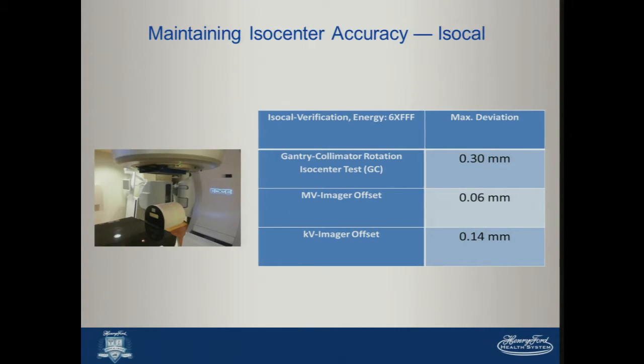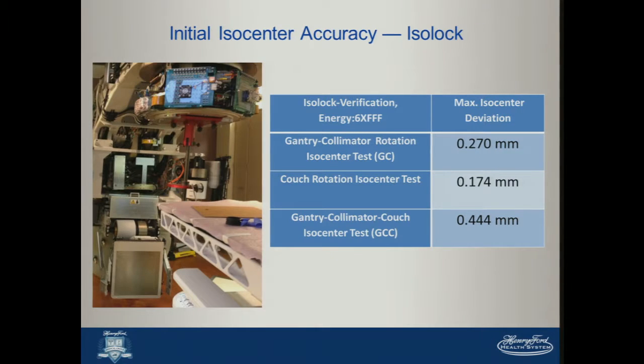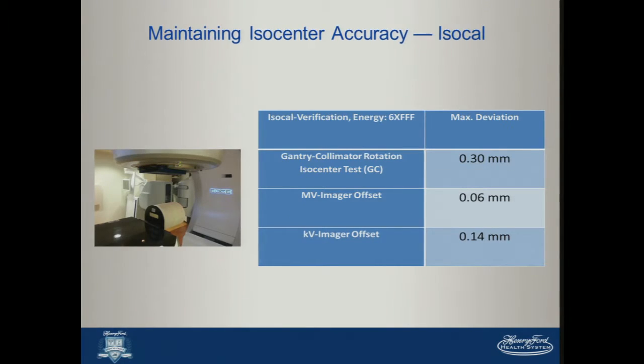Now, there are some nice tools that help you maintain that accuracy as you use the system to treat. One of those is the IsoCal system that is designed to bring the technology that's used for Isolock into the clinic so that the physics team can use it. It measures the isocenter position accurately using multiple gantry angles, and then measures the isocenter positions for the MV and KV images and writes an XML file to disk so that the system uses it to correct after each calibration, if you like, where the true isocenter of the imaging systems is, so that it's well aligned with the mechanical radiation isocenter.